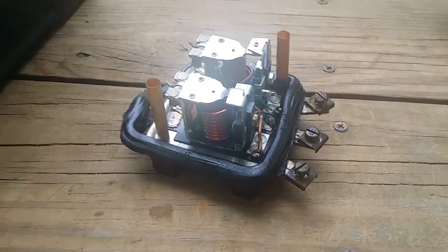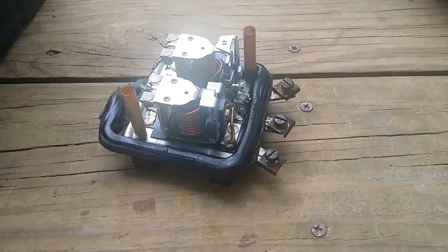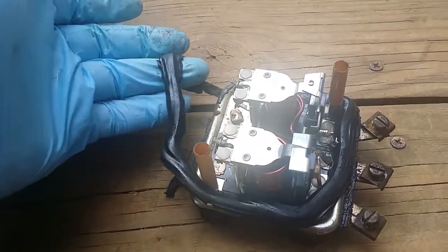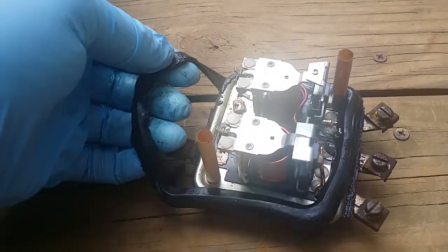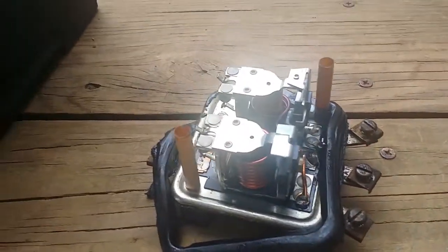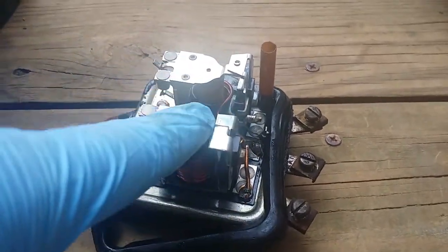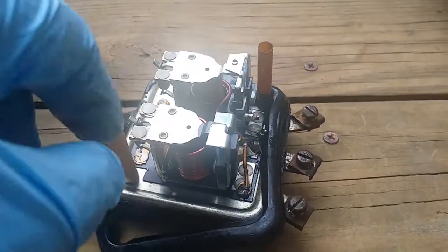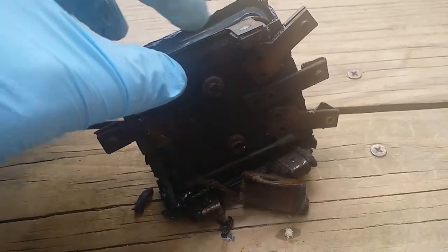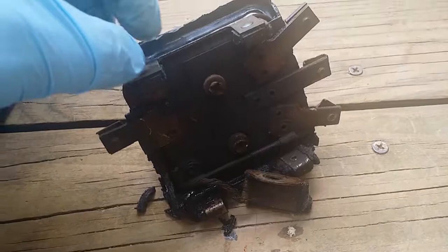Here I've removed the voltage regulator. One of the dilemmas was an additional dilemma — there was diesel leaking on this from the sediment bowl. And as you can see, diesel combined with rubber makes mush. Other than that it looks pretty clean. I'll probably test the coils, make sure that they're firing off, but they should be, and like I said it worked fine. On this back side you can see where the rubber, probably again from the diesel that had leaked on it.